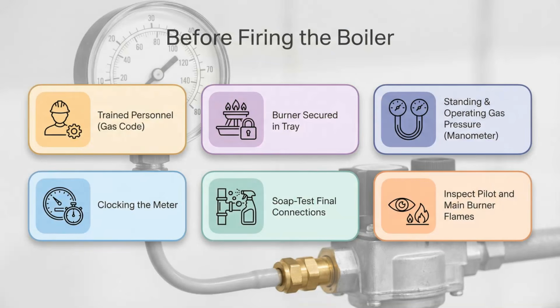Before firing, gas codes require trained personnel. The burner must be properly secured, then standing and operating gas pressures are checked with a manometer. Clocking the appliance verifies input matches the manufacturer specs. Final connections get soap tested, and both pilot and main burner flames are visually inspected per the manual.